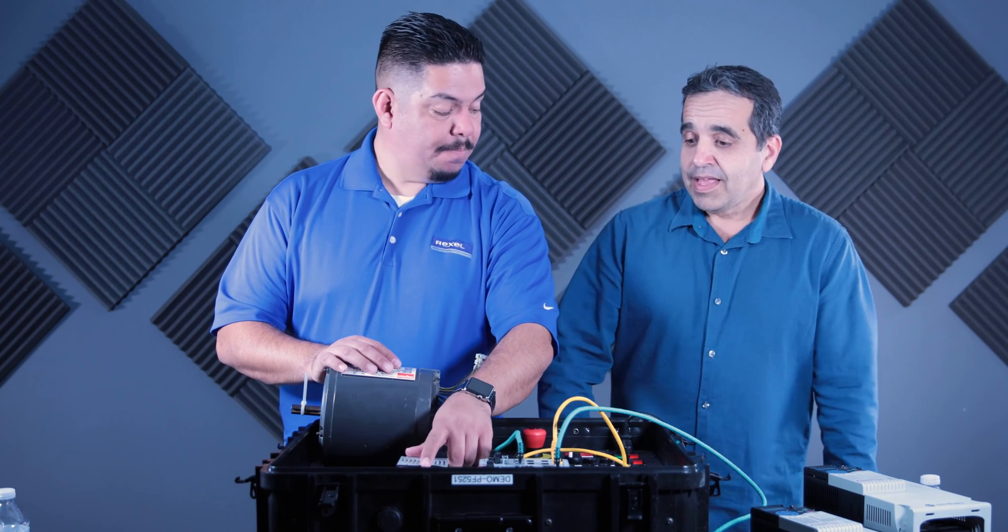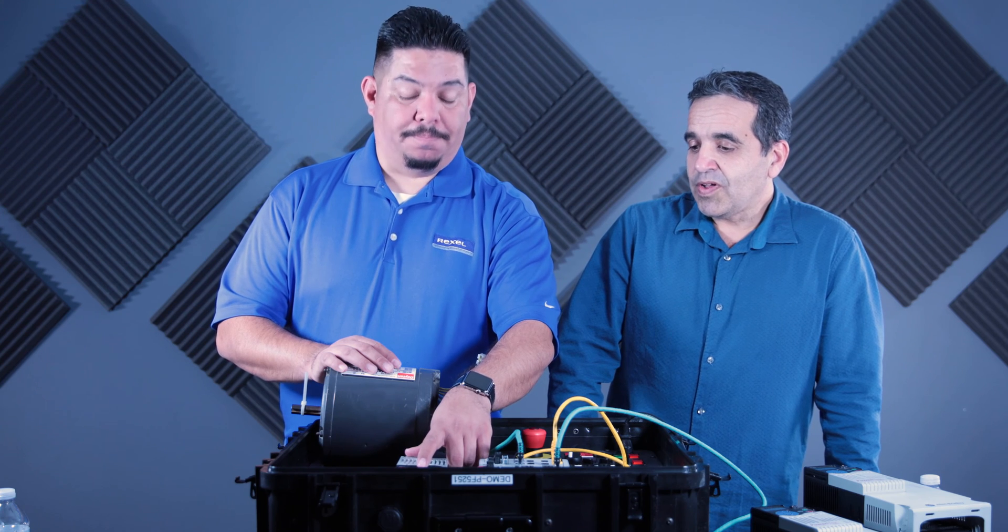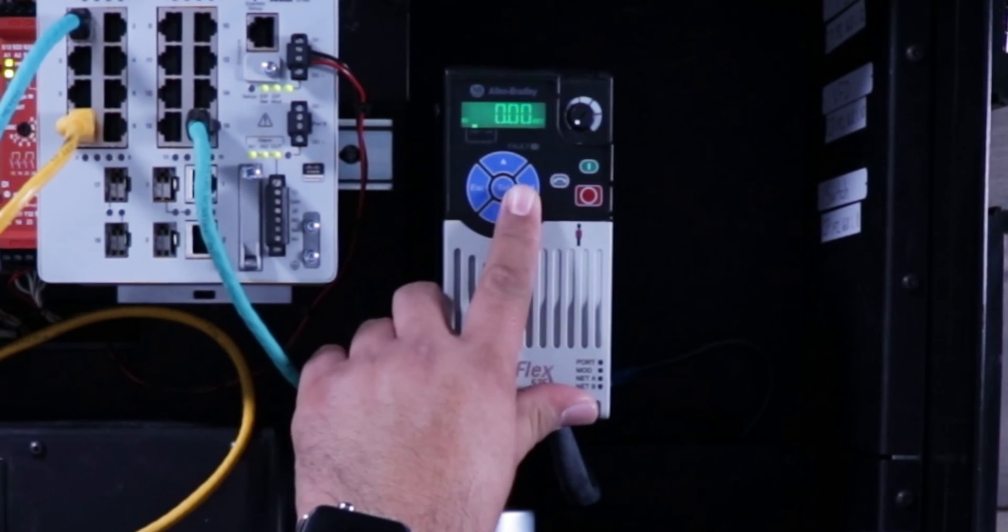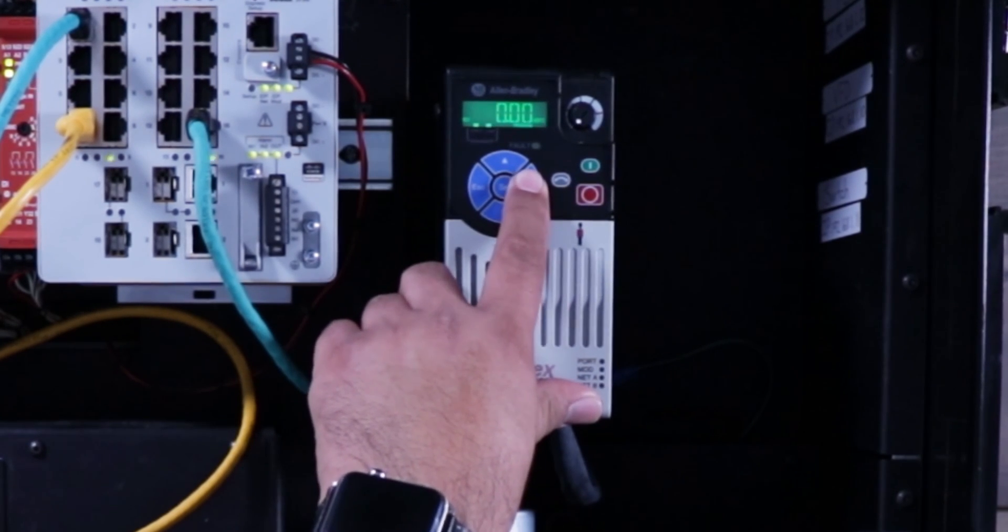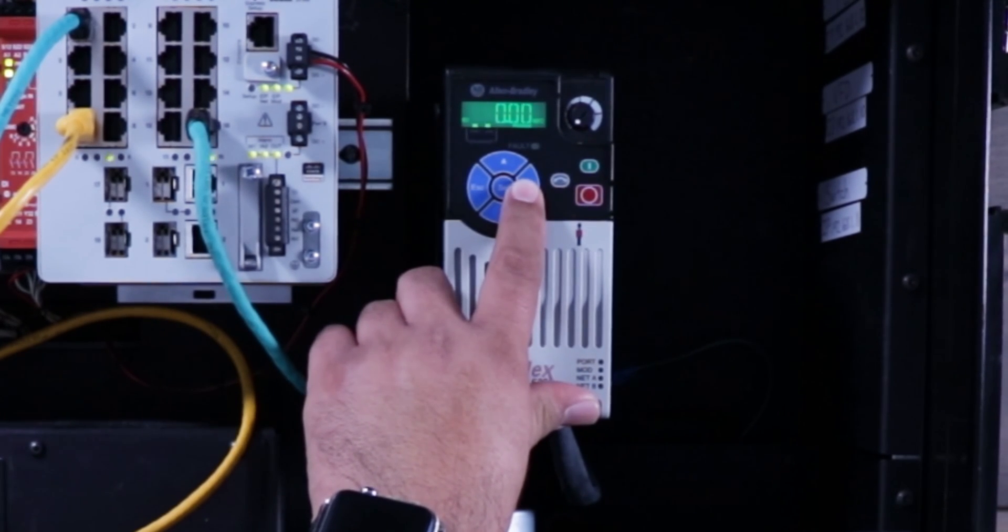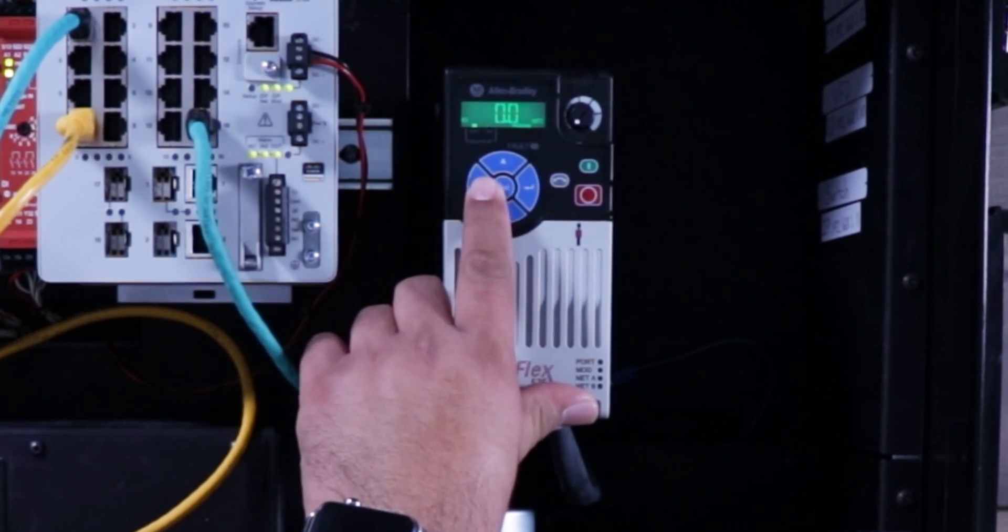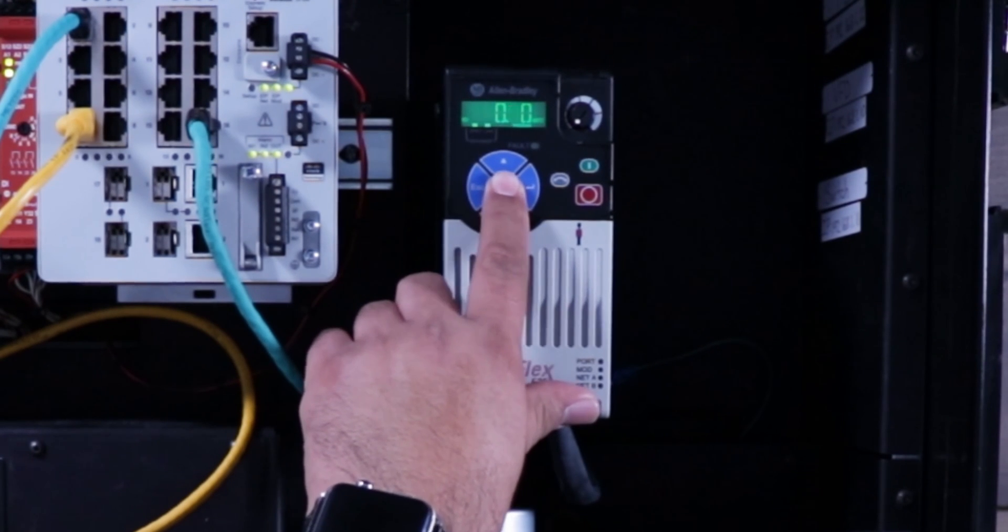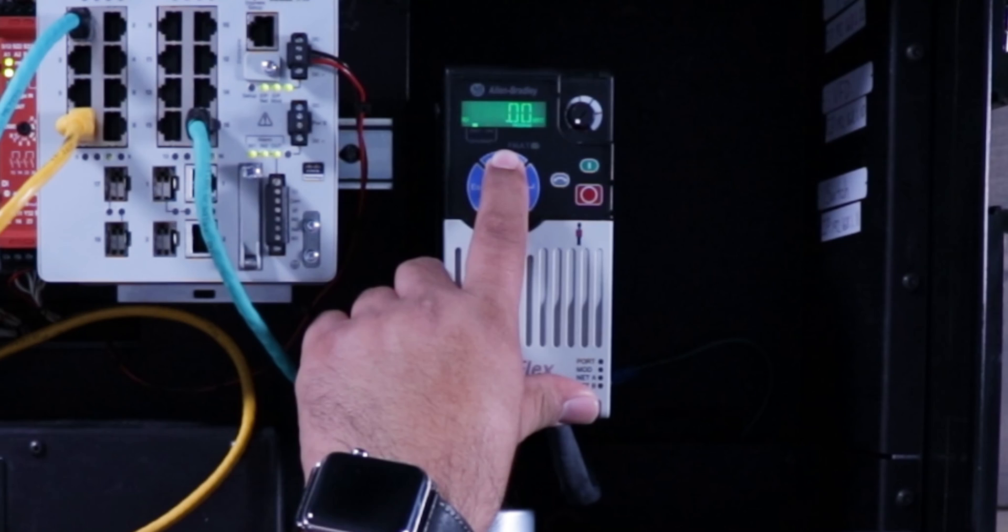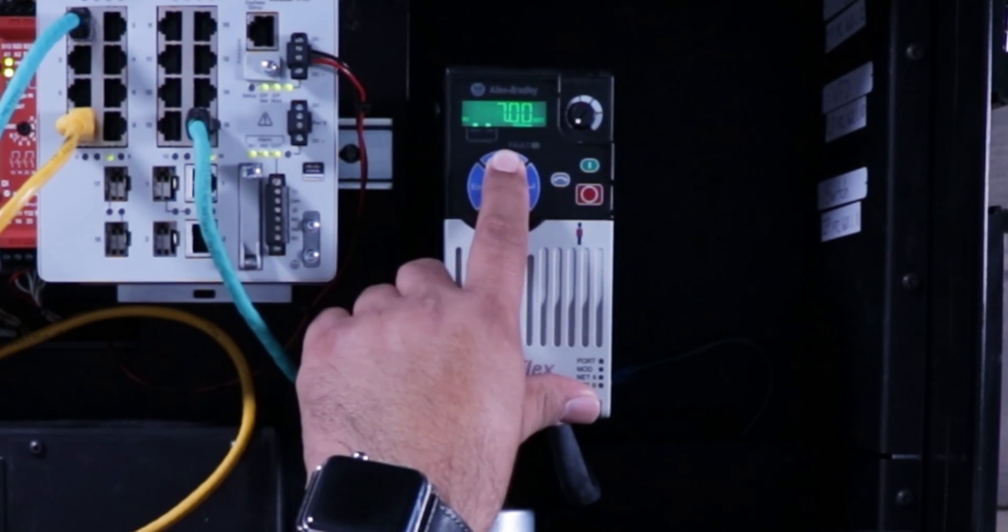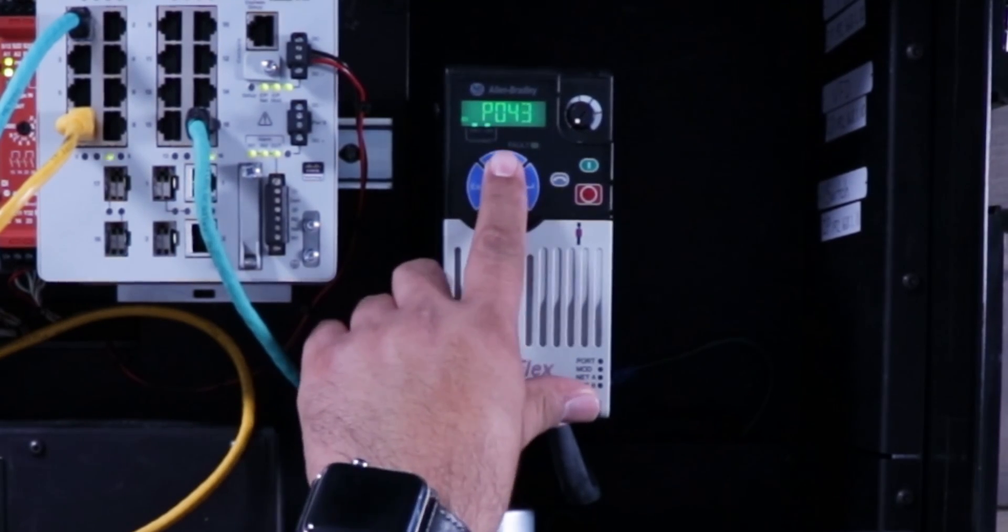So parameter 43 would be our minimum frequency. The slowest you want the motor to go before you can't go any slower. And again, let's go all the way down to zero for that. Typically, you don't want to run a VFD slower than 10. Some applications may require it. And you can do that with specific motors. But for the most part, 10 Hertz is, you're pushing it with 10 Hertz. So we've tried not to go below that. And that's pretty slow.